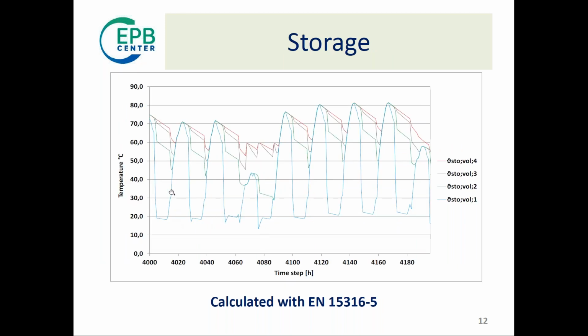As well as you can see here the dynamics in our, for example, storage. In this case, you see here this is a temperature in the lower part, and then progressively up to the upper part. And you can see, for example, when the cold water is coming in, of course, you cool down, and then, for example, here you are heating up with the solar, and then when you get to the upper temperature, you are heating the whole of the thermal solar. So you can see really the dynamics, and you can estimate what is the contribution of the thermal solar.